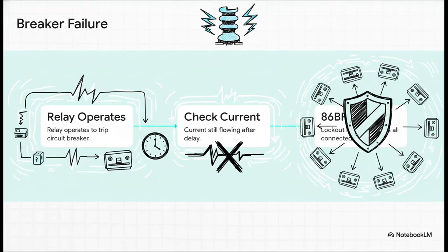Okay, we've covered the math, the zones, and the communications. But we have to face the absolute darkest scenario for any grid engineer. What happens when the relay does its job perfectly, sends the trip command, but the actual physical mechanical circuit breaker jams and just fails to open? Well, here is the chronological cascade. First, the distance relay detects the fault and commands a trip. Second, a timer starts and the system watches the current. If dangerous fault current is still flowing after a pre-selected delay, the system confirms the physical breaker is broken.